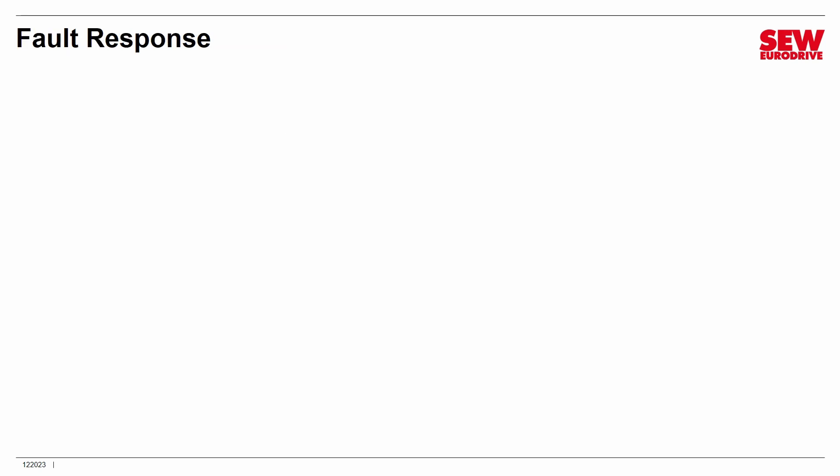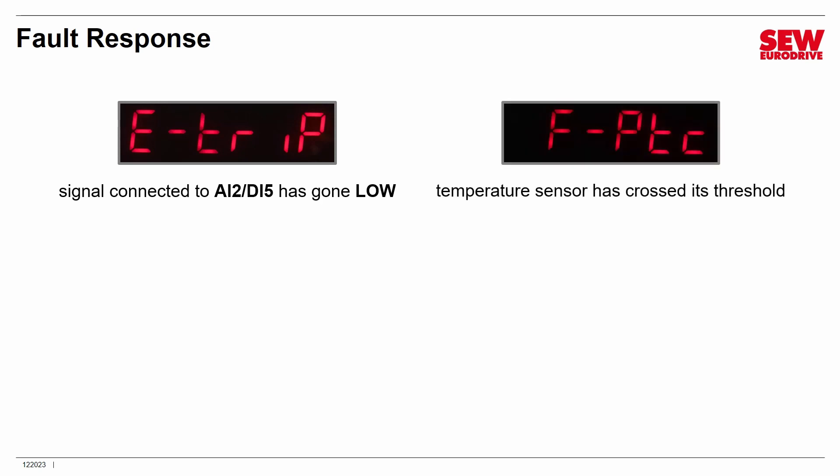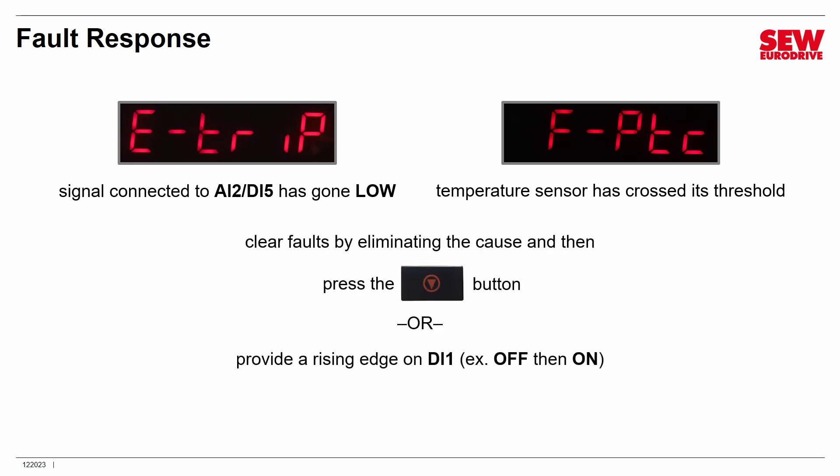If you have it wired as a generic fault sensor, when digital input 5 goes low you will get the message ETRIP on the VFD's display. If configured as a temperature sensor with its type set, you will see F-PTC instead — meaning the temperature sensor has tripped digital input 5. To clear the fault, first eliminate the cause (such as allowing the motor to cool), then clear the fault by pressing the stop button on the VFD or by providing a rising edge on digital input 1 — turning it off and then on again.